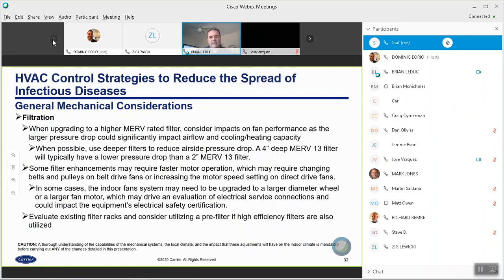Filtration, there are limits to the highest MERV rating that a given piece of equipment can tolerate. If you install it, you're going to have a higher pressure drop. That's going to affect your airflow capacity. They do have a recommendation to use deeper filters to reduce the pressure drop. I'm not an expert on filtration, but they recommend a 4-inch deep MERV 13 will have a lower pressure drop than a 2-inch. So if you're in a discussion with your customer about improving filtration, this is the guidance from our rooftop product managers.